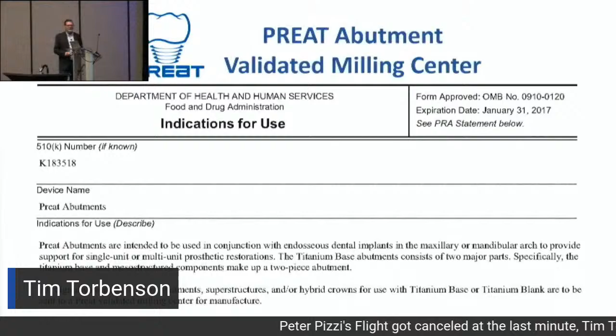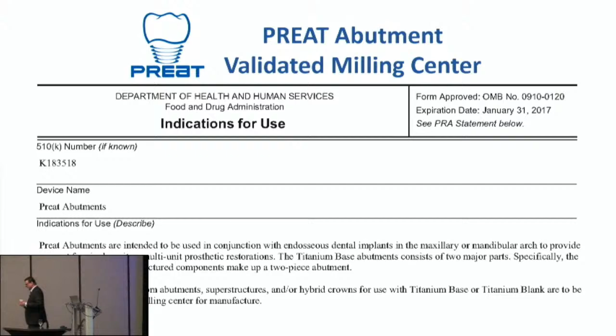So when this goes back, again, this started in 2010. This validated milling center terminology of the dental branch at the time, and in all of the 510(k)s that have cleared since that time for abutments, at the bottom, I apologize for this, but all digitally designed custom abutments and substructures and hybrids must be part of a validated milling center. All right. Same thing is true for BioHorizons. When it goes back there, it's the same thing. All digitally designed abutments and or wings, which includes the Ti bases, for the BioHorizons CAD/CAM abutments are intended to go to a BioHorizons validated milling center for manufacture. That doesn't matter how the abutments are designed. So this is when everything changed. 2017 is when the FDA came up with this requirement.